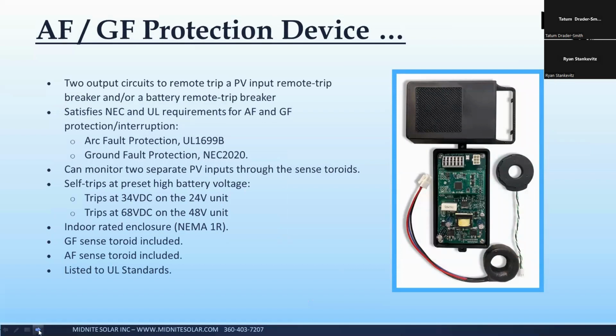So quickly, I'll touch on this one. This is something that we're getting ready to send off to be listed as well. This is what we're calling our standalone arc fault ground fault detection device. So if you get a system where you have to bring it to code and you need something to detect arc fault and ground fault, this can go in and remote trip a breaker for you and meet all those current requirements. So if you need more information on that, reach out to us, but we'll have a 24 and a 48 volt unit, and it comes as shown with the kit and the CTs, and then you purchase the right remote trip breakers to do what you need to do.